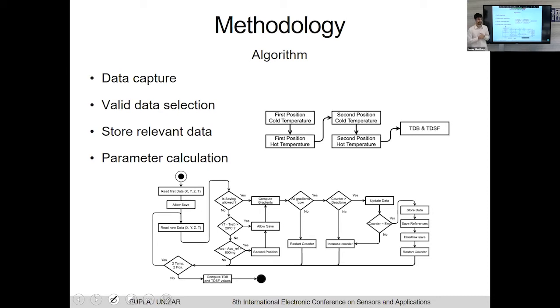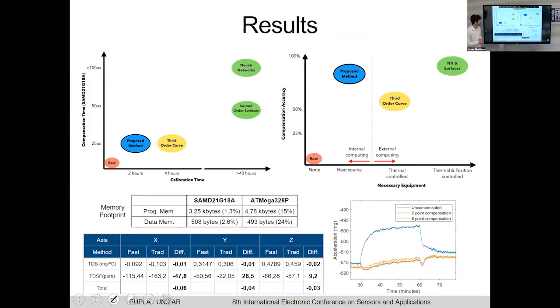Then it averages 1,000 values to ensure that all the noise is removed from the equation. Once all the four segments are obtained, it directly gives the user the thermal drift of bias and the thermal drift of scale factor to perform the compensations during the application.